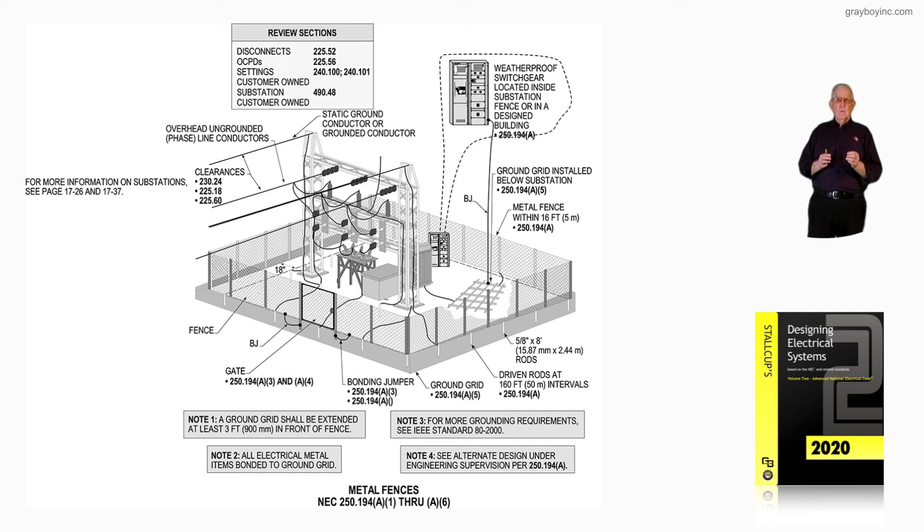Note 2 states that all electrical metal items are bonded to the ground grid, so all equipment inside that substation would be bonded into the grid in accordance with IEEE 80. Note 3 says for more grounding requirements, see IEEE 80, which covers maintenance and all rules pertaining to a substation. Note 4 addresses the alternative design under engineering supervision — see 250.194A.